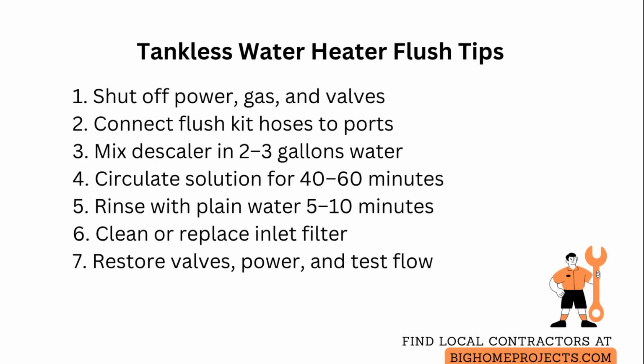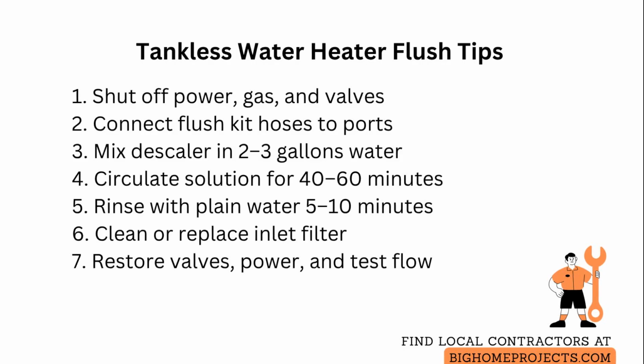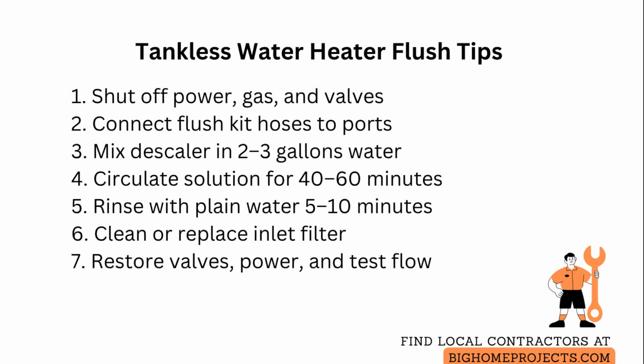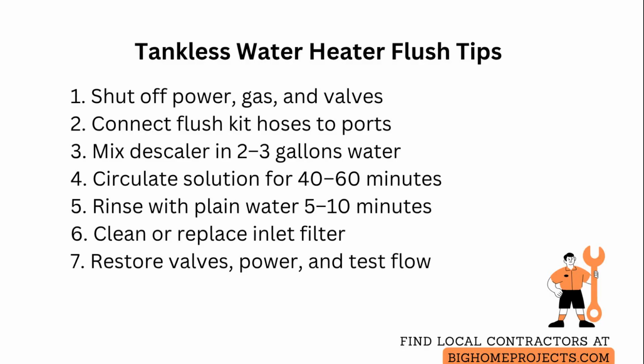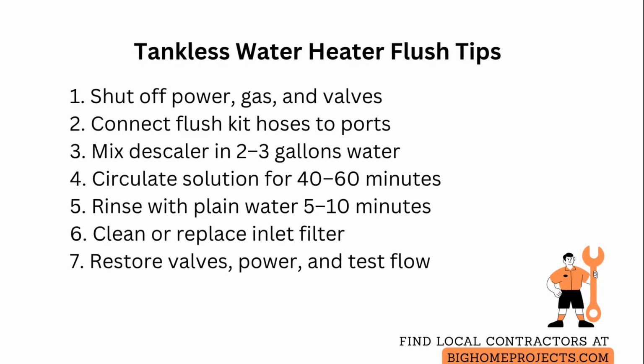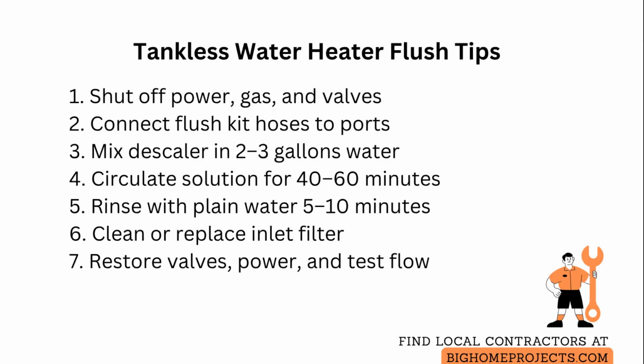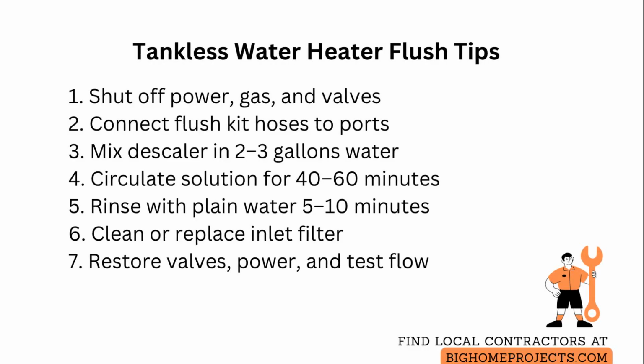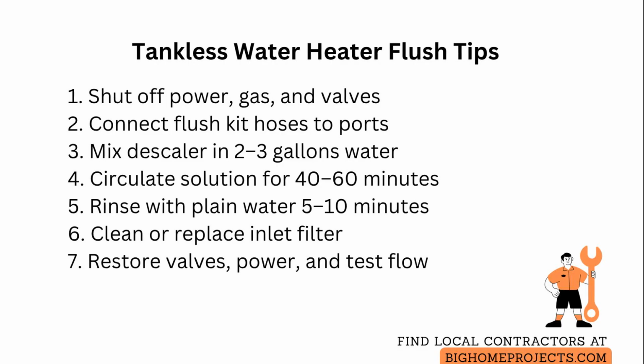After the descaling cycle, shut off the pump, close the service ports, disconnect the hoses, drain the bucket, then run plain water through the unit for 5 to 10 minutes using the pump to flush out any remaining solution. Finally, clean or replace the inlet water filter screen, reopen the main valves, restore power or gas, and run hot water to confirm stable flow and temperature. Do this once per year in soft water areas and twice per year in hard water areas.